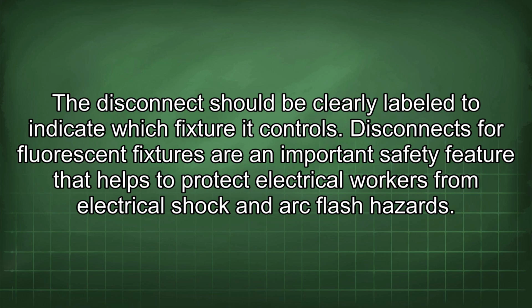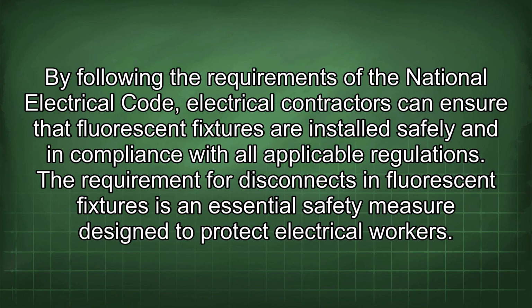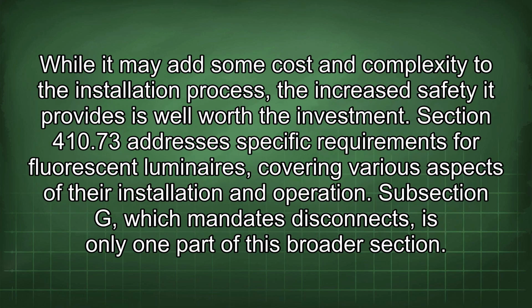Disconnects for fluorescent fixtures are an important safety feature that helps to protect electrical workers from electrical shock and arc flash hazards. By following the requirements of the National Electrical Code, electrical contractors can ensure that fluorescent fixtures are installed safely and in compliance with all applicable regulations. The requirement for disconnects in fluorescent fixtures is an essential safety measure designed to protect electrical workers.